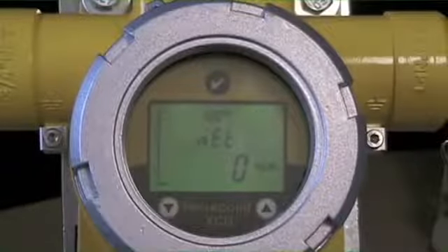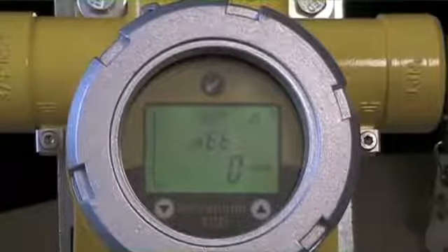In this segment, we're going to concentrate on setting the sensor range for the SensePoint XCD. In certain applications, customers want to change the sensor output for carbon monoxide or any of the gas types that are supported. The instrument comes factory defaulted in certain ranges depending on those gases, but we give you the option of changing that range or that output so that you can optimize the sensor to your particular application.